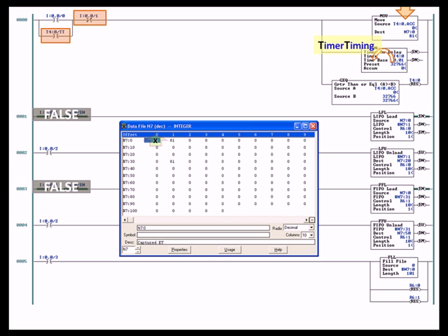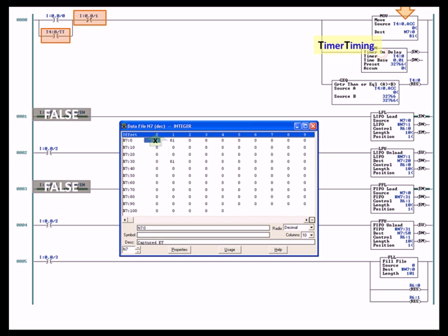And on every single program scan, the move instruction, which is a word copy, copies the value in the accumulate register of timer data type T4:0 into the integer N7:0. So that value, even though right now it's static in the image you're looking at, 81, it's actually if the logic was executing, would be going up very rapidly towards 32,766.